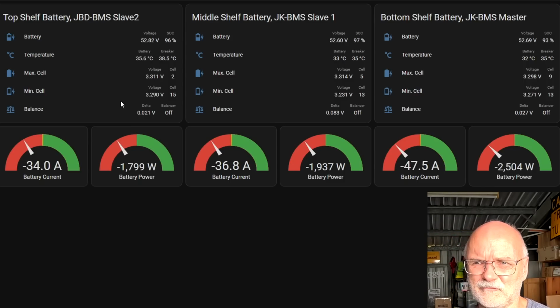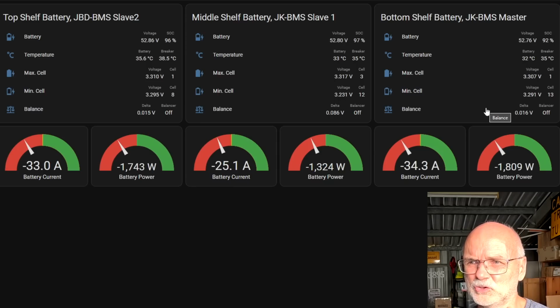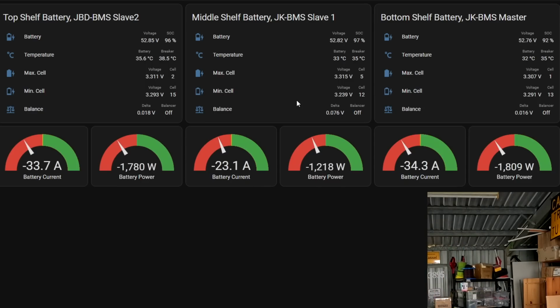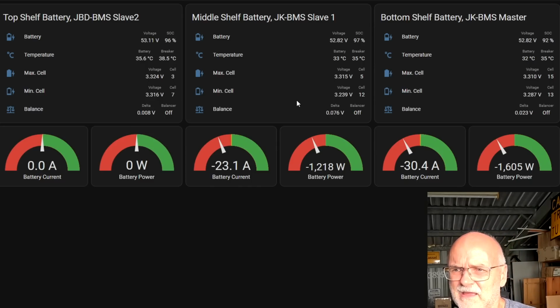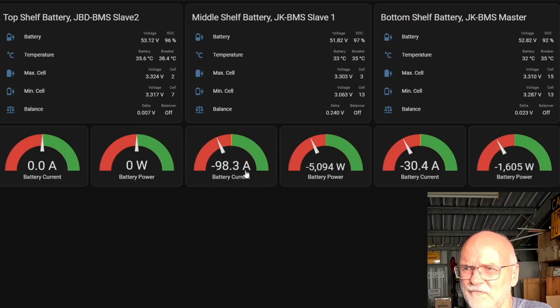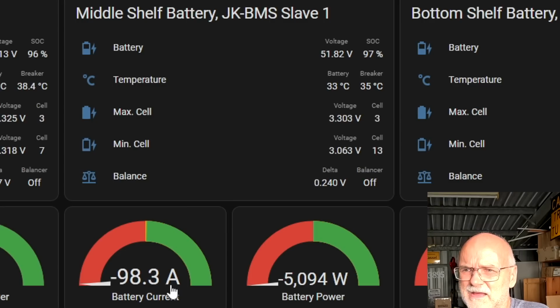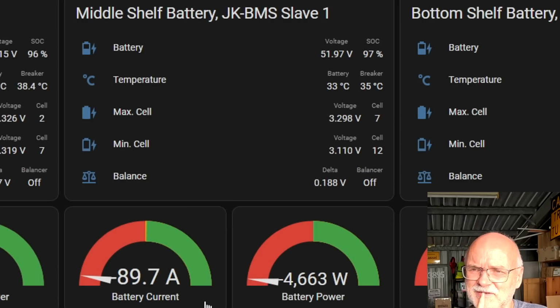And I'm turning off the top battery and bottom battery now, and we're running the whole show only from the middle shelf battery. Is that possible from the current? Yes, it is. Okay, off. So we should see 0 here for these two batteries, and a maximum current here for this battery. 100 amps discharging, nice, it's a 200 amp BMS, but only a 100 amp circuit breaker.